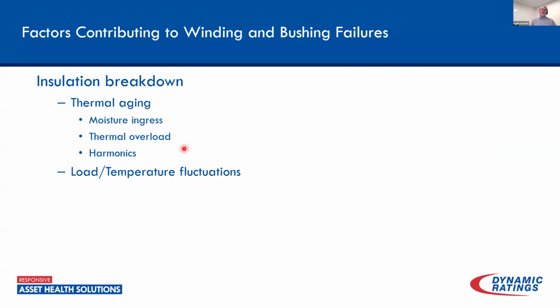So to begin with, when we look at the factors contributing to these transformer failures, one of the big ones that we talked about is insulation breakdown. Our previous speaker talked a little bit about some of the tests you can use to identify insulation breakdown. We're going to focus more on online characteristics and how this can impact it. Of course, moisture was one of the things that he addressed at the end of his presentation. Moisture, again, can have a significant impact on the thermal aging of the transformer and greatly shorten its life. What people probably don't recognize is that when you have load and temperature fluctuations, as you have that expansion and contraction of the oil, whether it's in the transformer or in the bushing, there's always a possibility for moisture ingress to increase on that transformer.